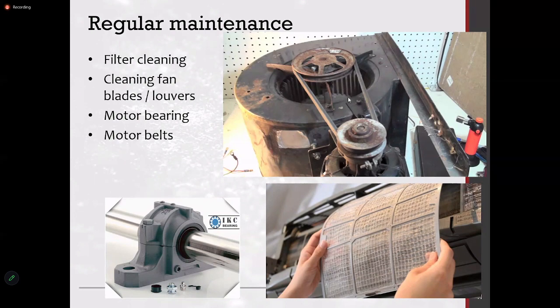So sometimes you also have to wash the indoor part. At least once a year or twice a year, they actually wash not only the outdoor coil fins but also the indoor fins, so that you take off any dust which has passed the filter and come inside and which is clogged inside the fins. So that is one key important thing.